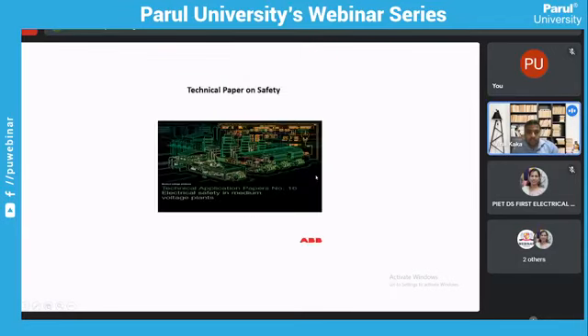They should not ignite due to the effect of hot gases or incandescent liquids; the indicators are pieces of black cotton fabric, as I said. The object of this test is that after initiating an internal arc inside an enclosure, all these test objects should remain in place, with no major deformations and no fire catching on any of the cotton fabric indicators. That ensures the switchgear is sufficient to cater for an internal arc for at least the time for which it has been tested. Also, criteria number 5 is that your earthing point should not get disconnected, and earthing still remains in place. So that's how it's tested.